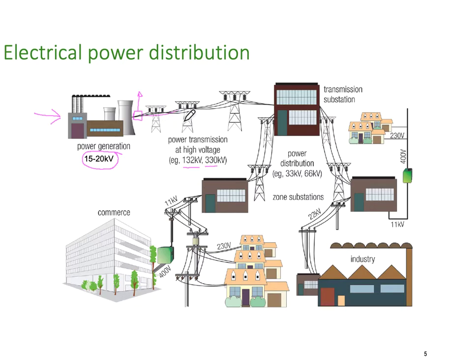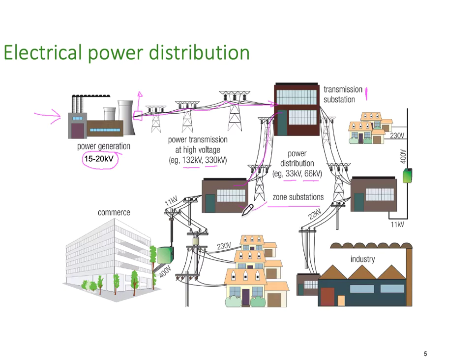We transmit through those large towers you see dotted across the landscape to large distribution substations. You can tell the distribution substation by the insulator columns — stacks of big porcelain plates that are often 5, 6, or 7 metres tall. You often see big aluminium corona rings to help with very high voltage discharge. From there, we distribute to zone substations, often at 33 or 66 kV, and sometimes even 132 kV, where voltage is again reduced through transformers.